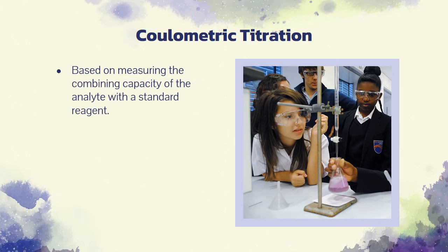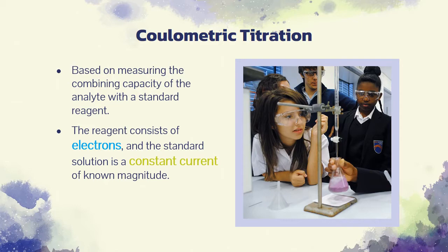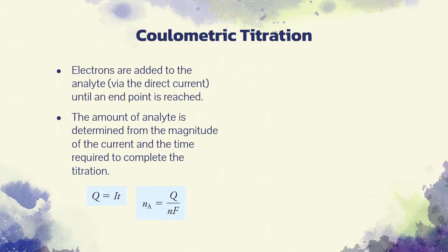Coulometric titrations are similar to other titrimetric methods in that the analyses are based on measuring the combining capacity of the analyte with a standard reagent. In the coulometric procedure, the reagent consists of electrons, and the standard solution is a constant current of known magnitude. Electrons are added to the analyte via the direct current or to some species that immediately reacts with the analyte until an endpoint is reached. At that point, the electrolysis is discontinued. The amount of analyte is determined from the magnitude of the current and the time required to complete the titration.